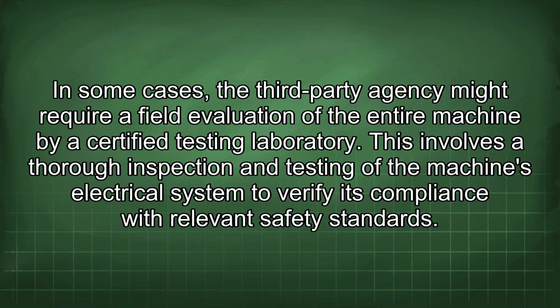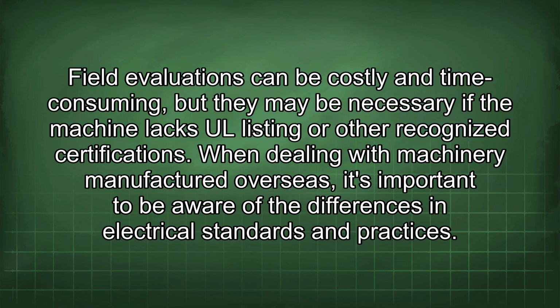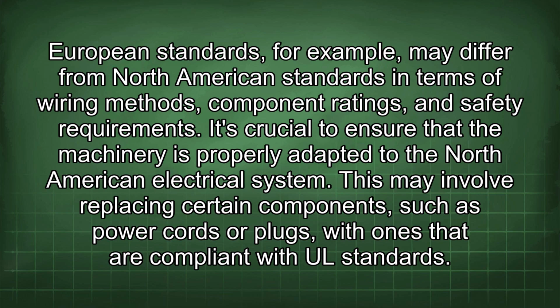In some cases, the third-party agency might require a field evaluation of the entire machine by a certified testing laboratory. This involves a thorough inspection and testing of the machine's electrical system to verify its compliance with relevant safety standards. Field evaluations can be costly and time-consuming, but they may be necessary if the machine lacks UL listing or other recognized certifications. When dealing with machinery manufactured overseas, it's important to be aware of the differences in electrical standards and practices. European standards, for example, may differ from North American standards in terms of wiring methods, component ratings, and safety requirements. It's crucial to ensure that the machinery is properly adapted to the North American electrical system.